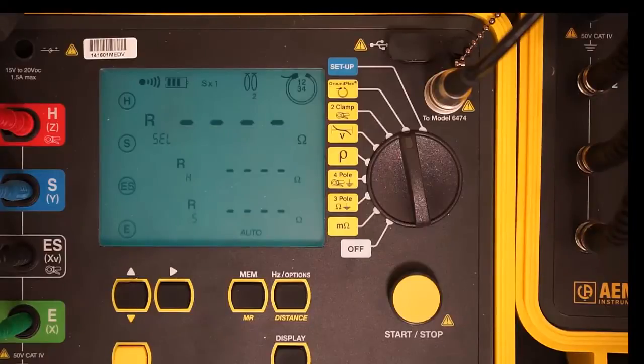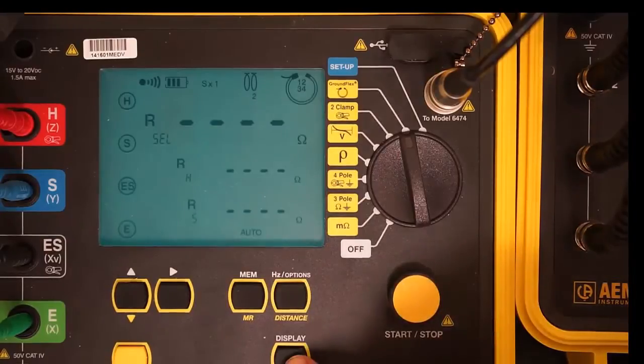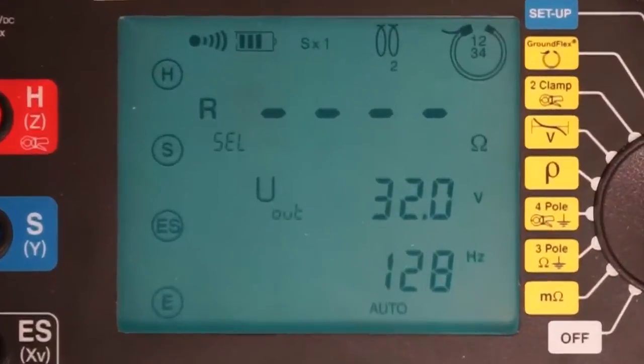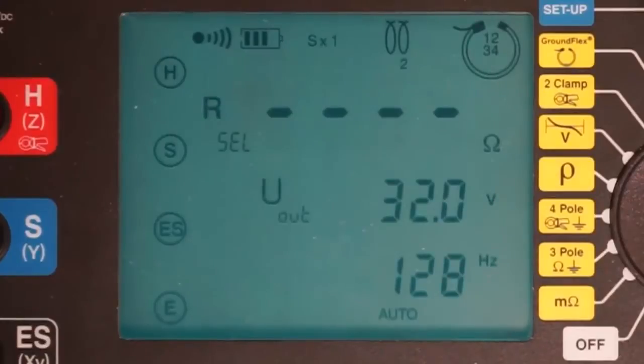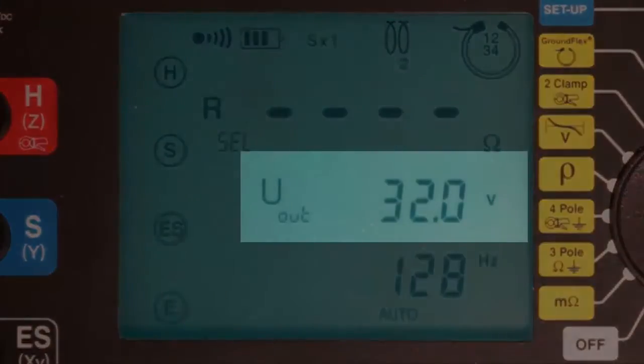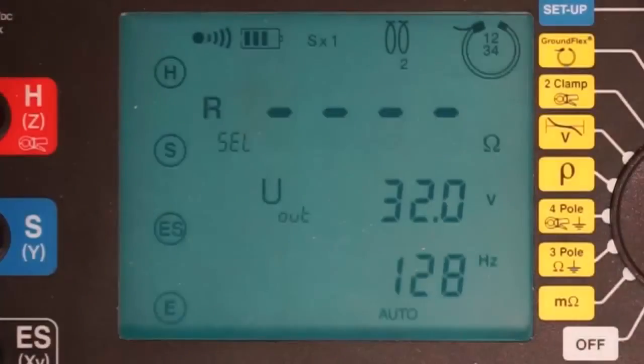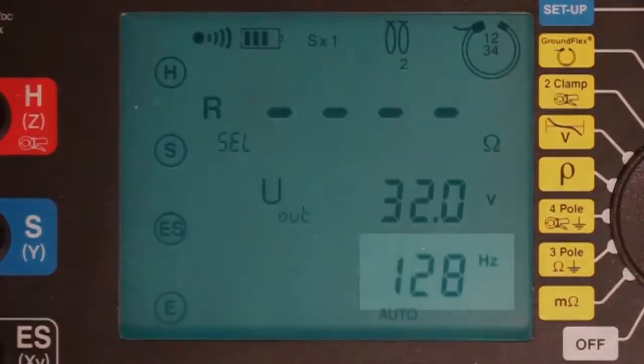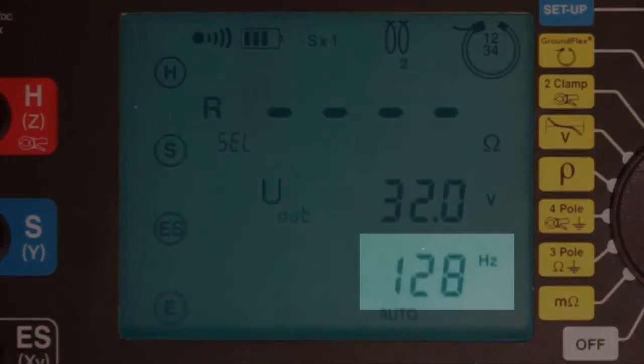Press the display button once on the Model 6472. The screen shows 2 important values. The first is labeled U sub out. This is the output or injector voltage we will use to perform our tests, which in this case is 32 volts. The second is the baseline frequency that will be used. In our demonstration, this is 128 Hz.